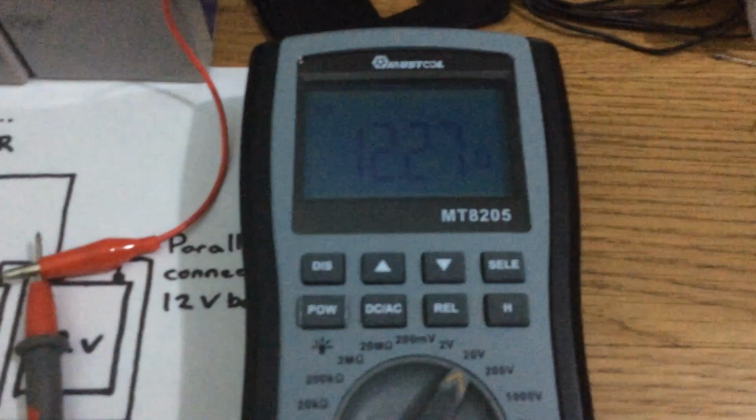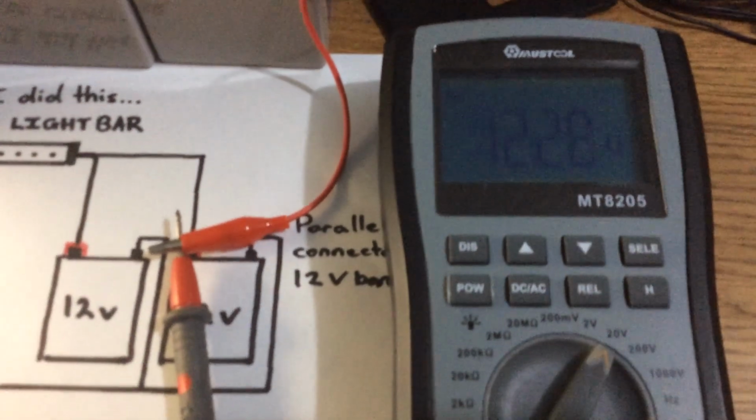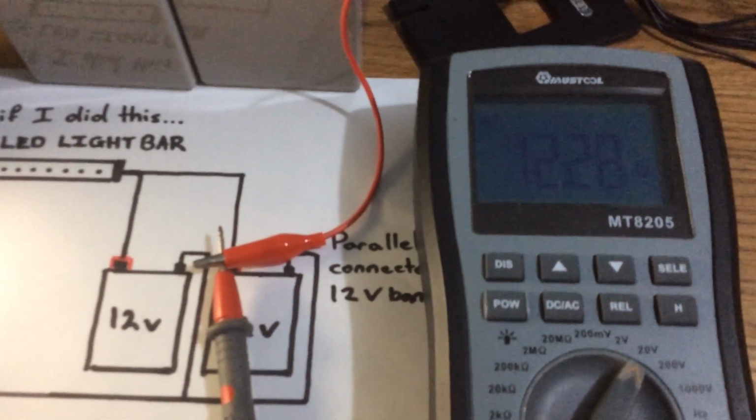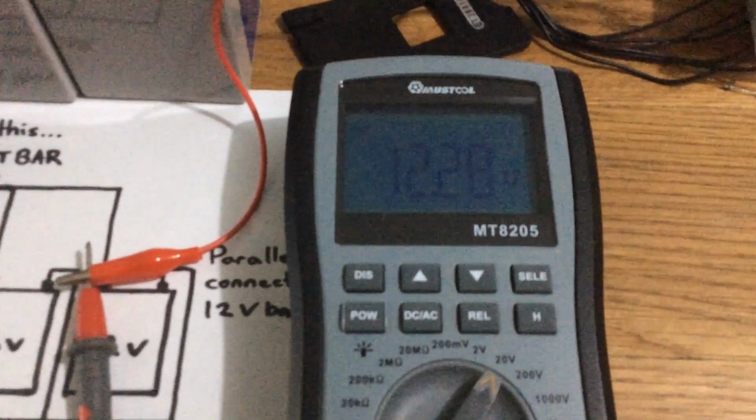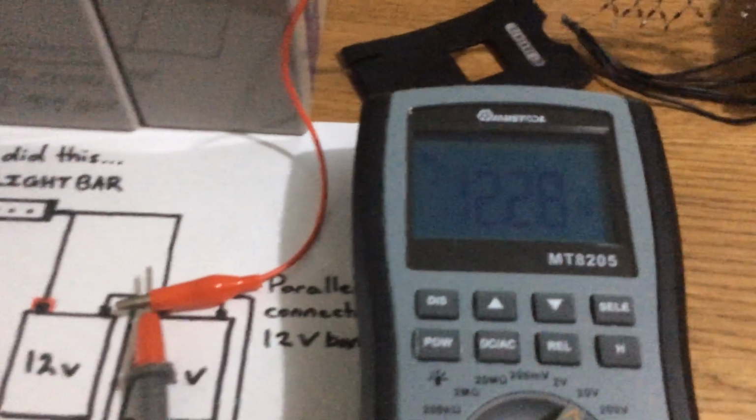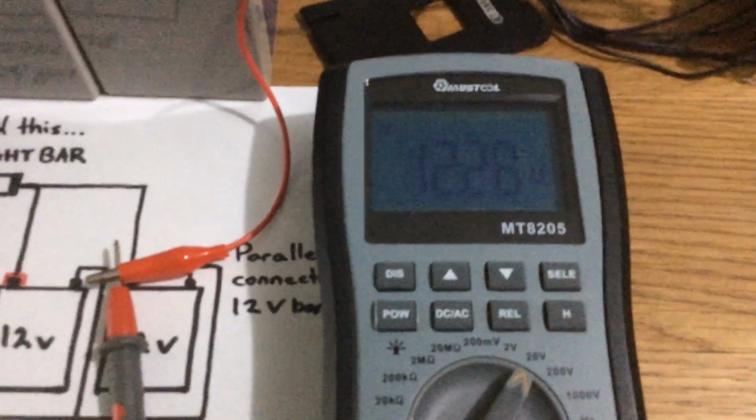And the light will stay pretty much that intensity for the entire duration until these drive batteries over here. So hang on, flip that light around again, otherwise we can't see anything. So these drive batteries here, when that gets down to, what would it be, 24.2 volts, then that would be time to disconnect that set of batteries. Otherwise, if you continue to flatten them beyond that, they will be damaged. The thing about lead acid batteries is you can only use 50% of their rating. Once you get down to lower than 50% capacity, you're actually damaging them permanently. So there's very little recovery from that situation.